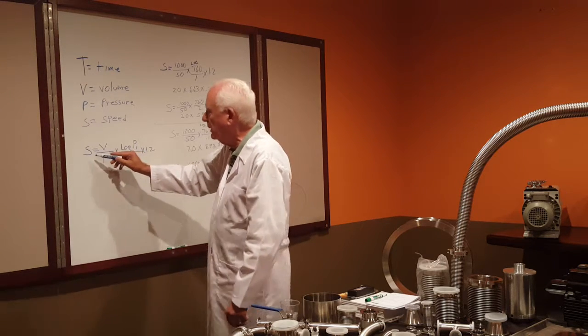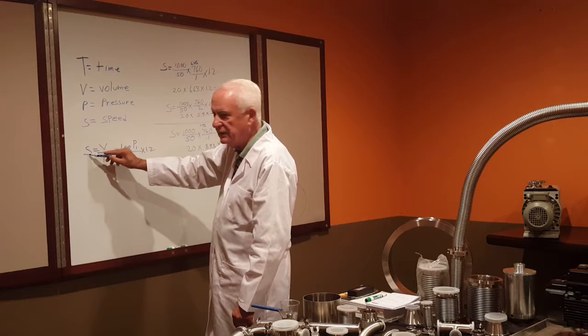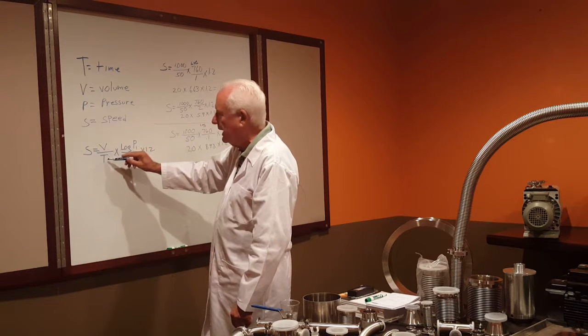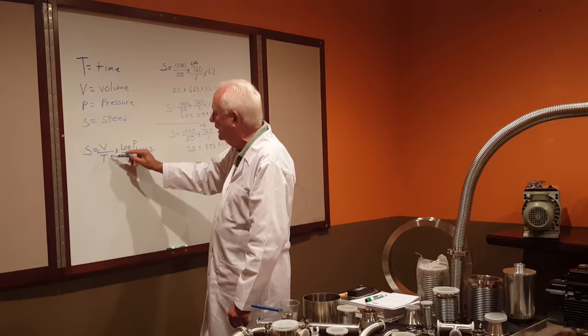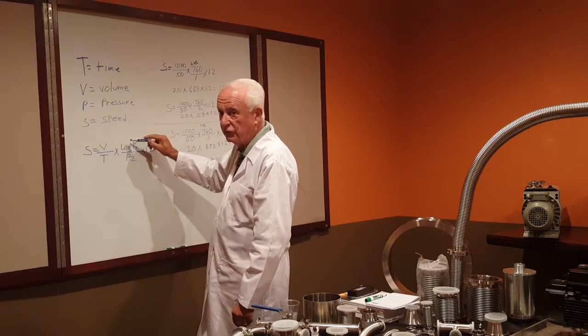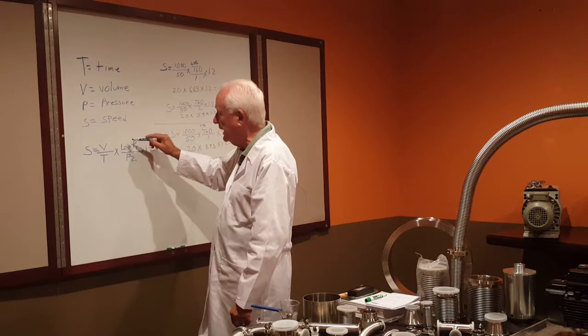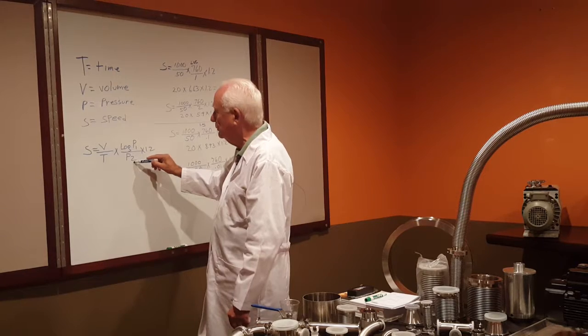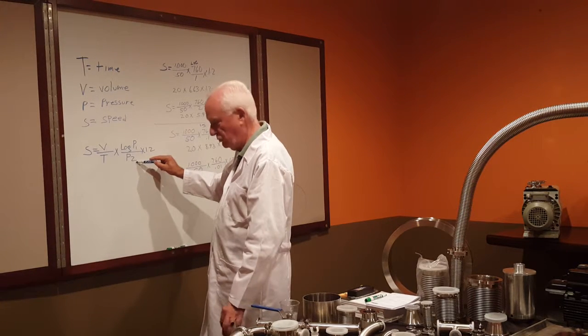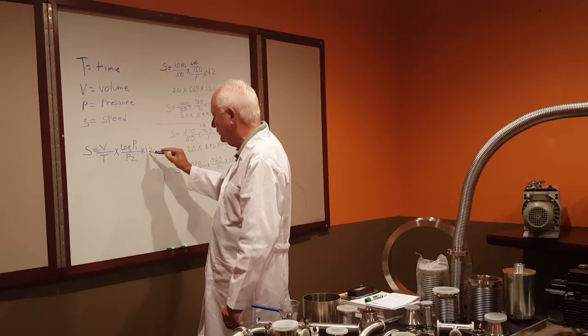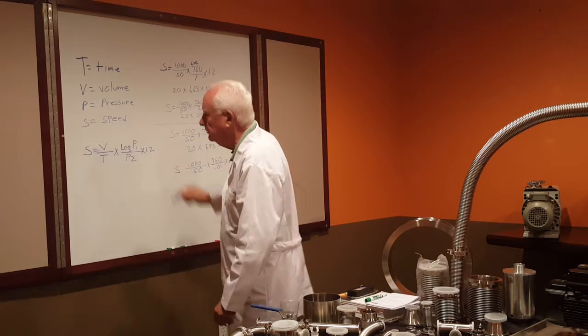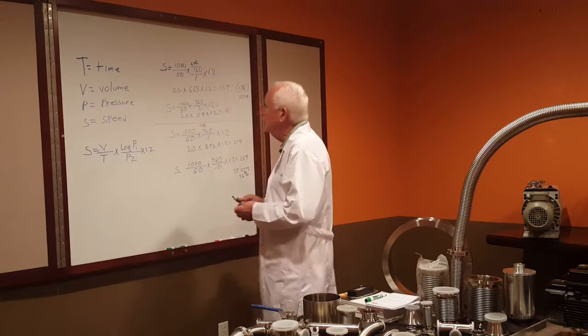The formula we use to determine the pump speed that you need is: we take the volume divided by the time you give us, times the log of the initial pressure — which is usually atmosphere — down to P2, which is the pressure you tell us you want to achieve. We have a system factor of 1.2.